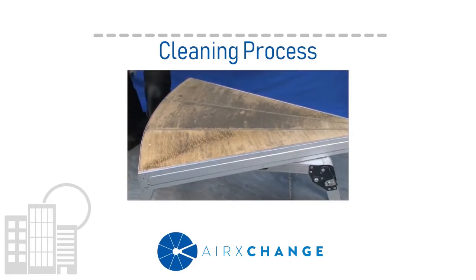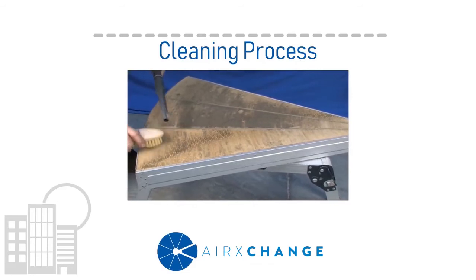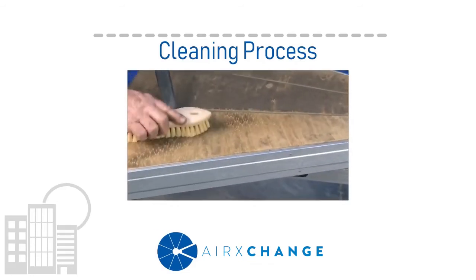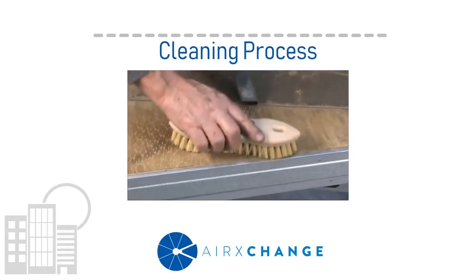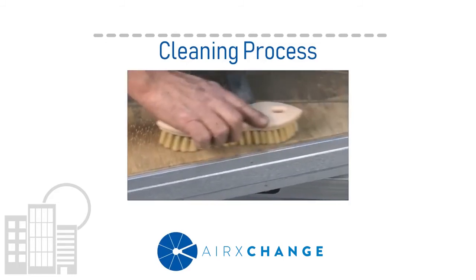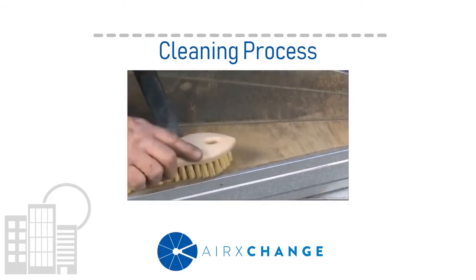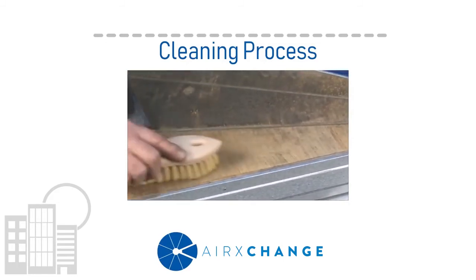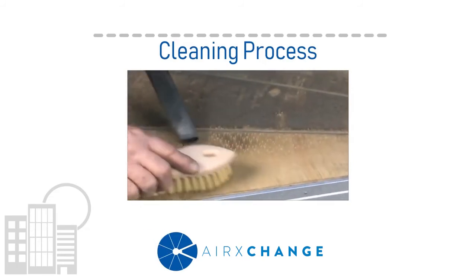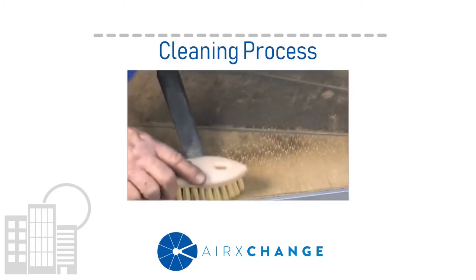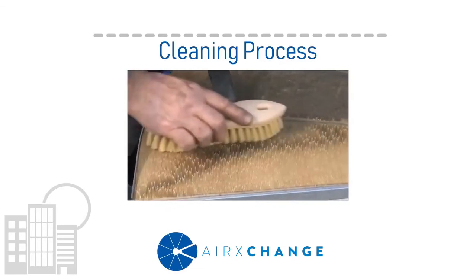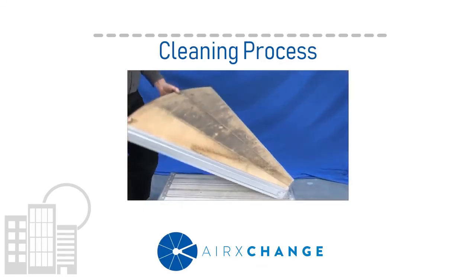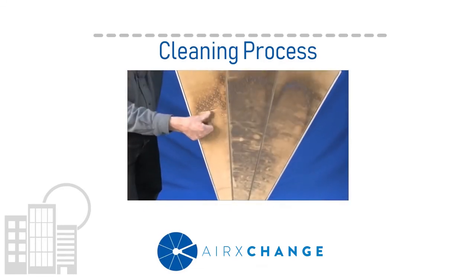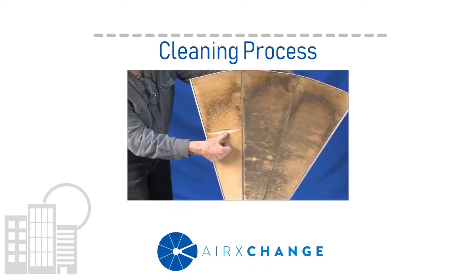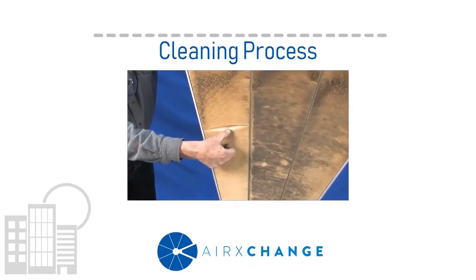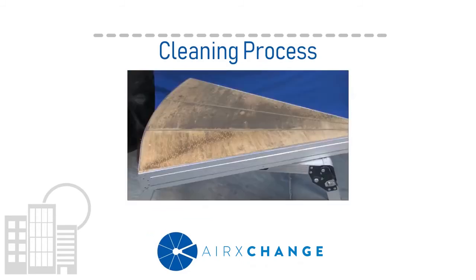For segments that have a light layer of dust on the face of the wheel, a dry method of cleaning may be used. Using a coarse brush and a vacuum, lightly brush the face of the segment while following along with the vacuum. Once the process is complete, flip the segment over and repeat the process for the opposite side. Once both sides are clean, check to make sure that there's no sticky residue left on the face of the wheel. If all clean, place aside and repeat process for the rest of the segments.